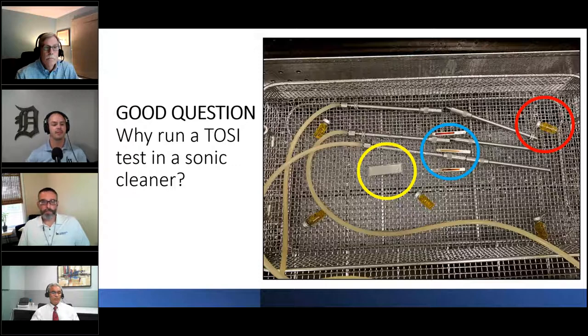You can see in the red circle, going back to that cavitation, we want to make sure that there's ultrasonic energy going through our bath. That is a Sonicheck test in the red circle. This is a vial that starts out green in color, and in the presence of cavitation or ultrasonic energy it will turn yellow.